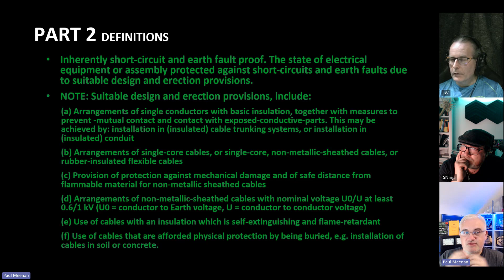Things like short circuit proof, we don't test that in our EICs in systems. Well, Dave, let's go into the note, because this is quite a long one. So there is a note that says suitable design and erection. It's nice to see a note about that. Suitable design erection provisions include a number of lettered items. The first one is A, arrangement of single conductors with basic insulation together with measures to prevent mutual contact and contact with exposed conductive parts. This may be achieved by installation in insulated cable trunking systems or installation in insulated conduit.